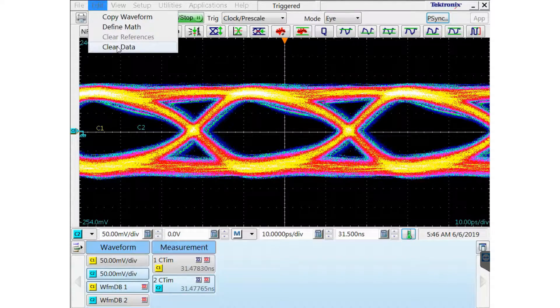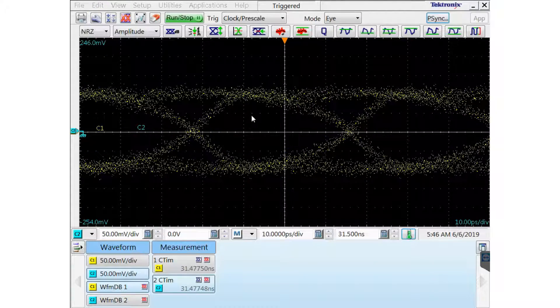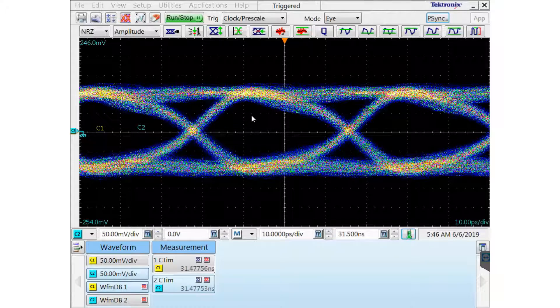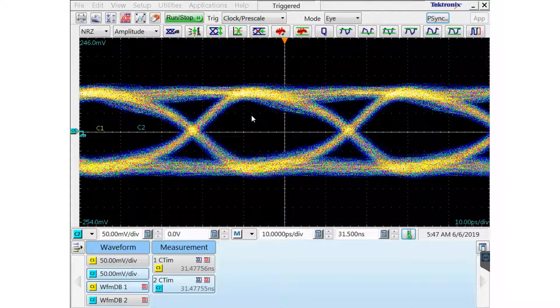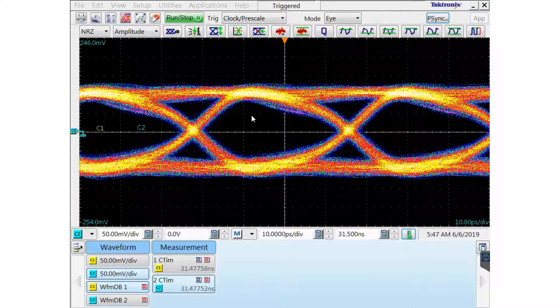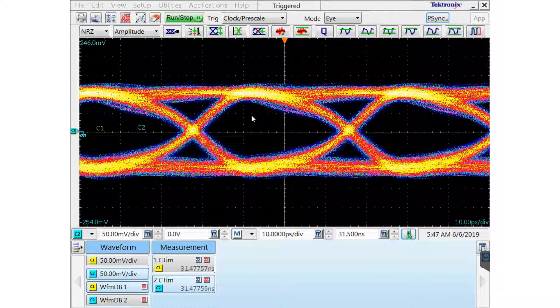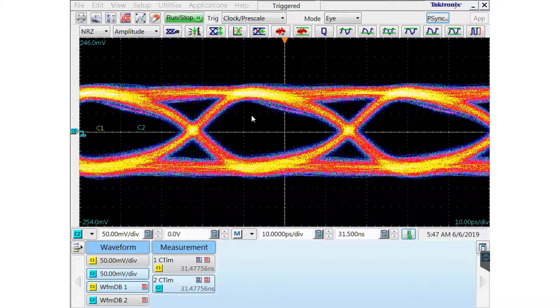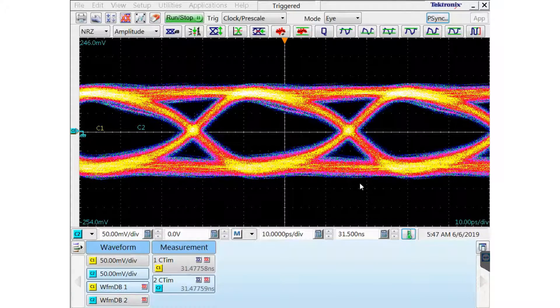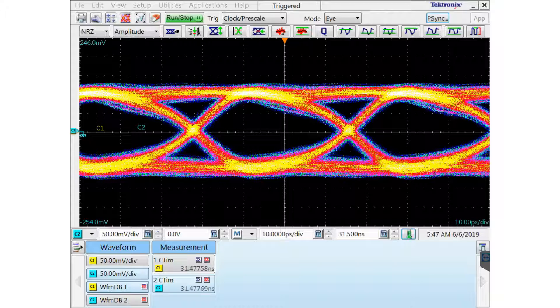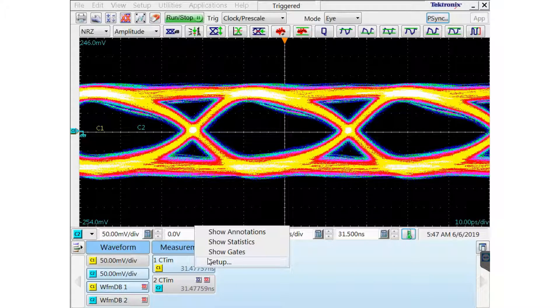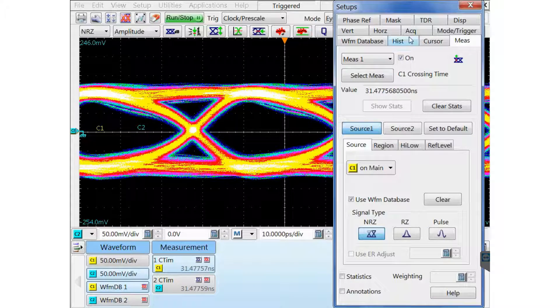I'm going to clear the database edit menu clear data just to refresh the measurement data. And as you can see in my values, 31.477, very close. Very close. It's a good deskew.